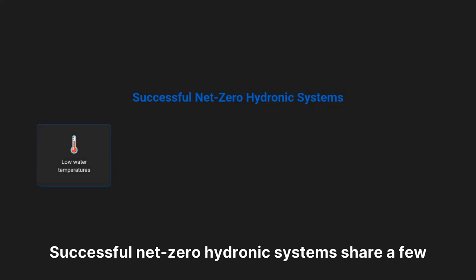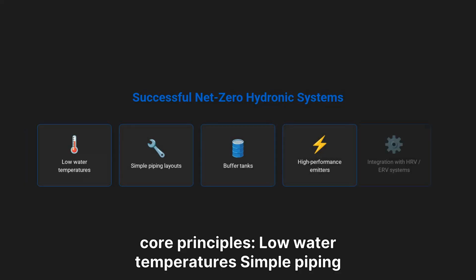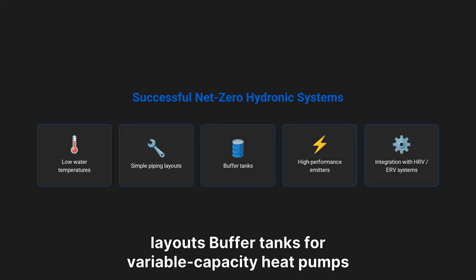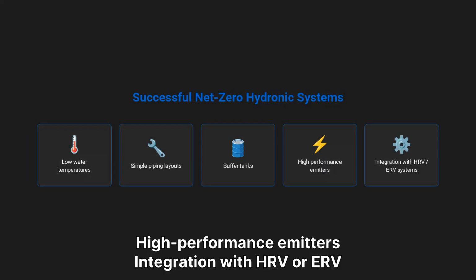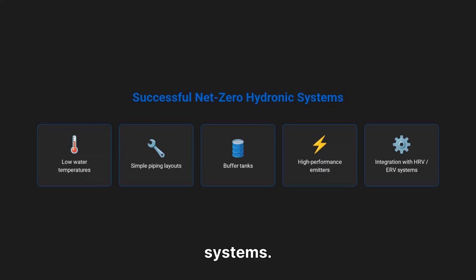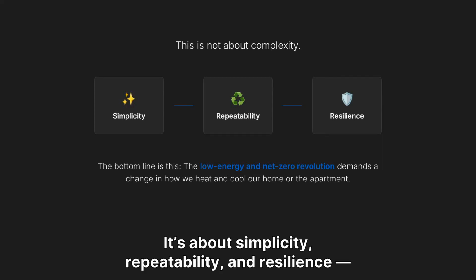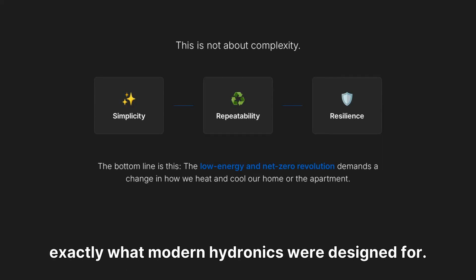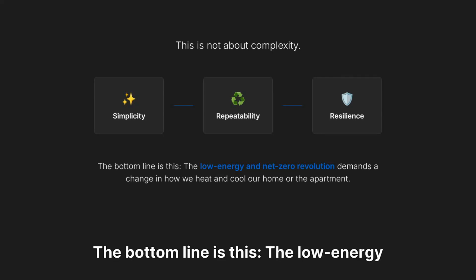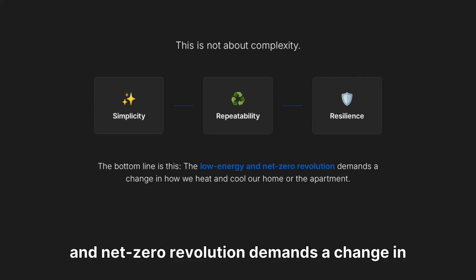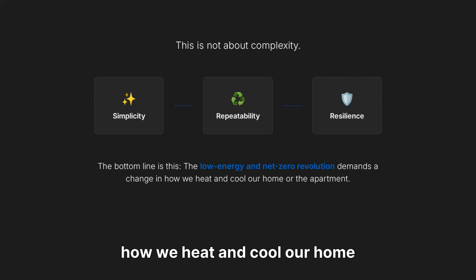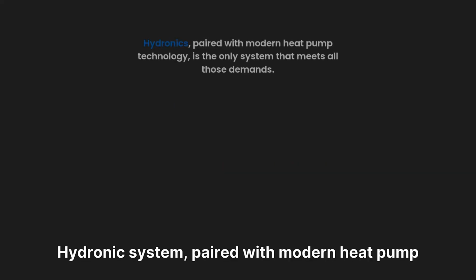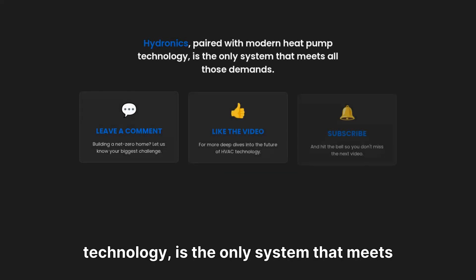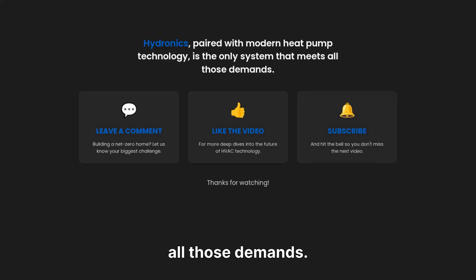Successful net zero hydronic systems share a few core principles: low water temperatures, simple piping layouts, buffer tanks for variable capacity heat pumps, high-performance emitters, and integration with HRV or ERV systems. This is not about complexity. It's about simplicity, repeatability, and resilience, exactly what modern hydronics were designed for. The bottom line is this: the low-energy and net zero revolution demands a change in how we heat and cool our home or apartment. A hydronic system, paired with modern heat pump technology, is the only system that meets all those demands.